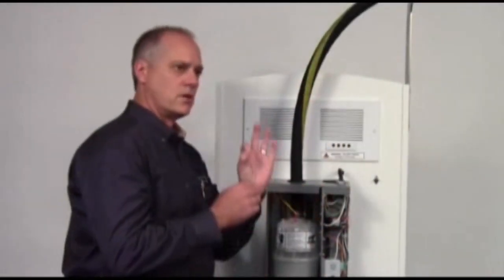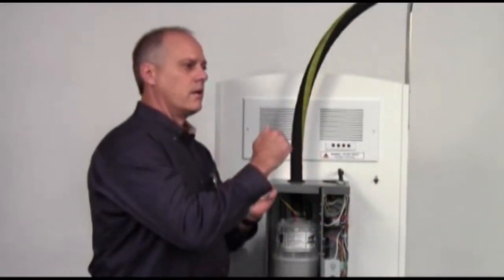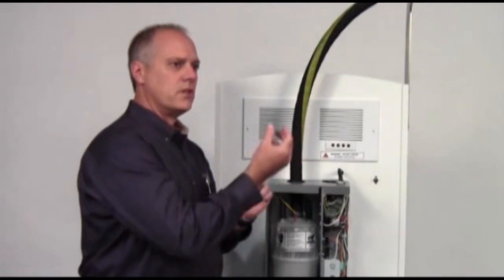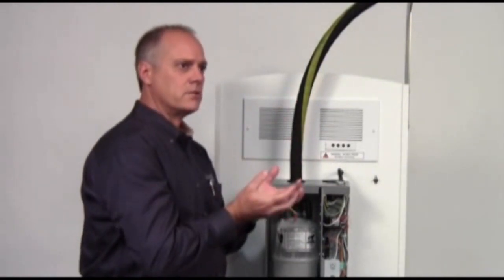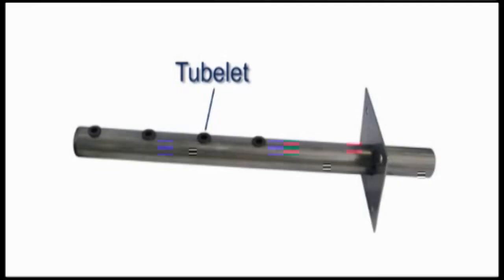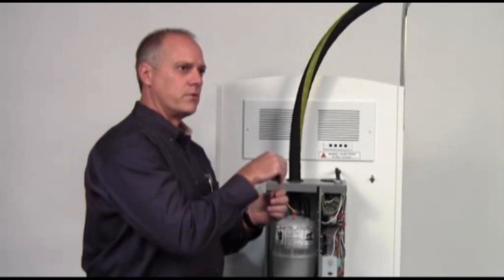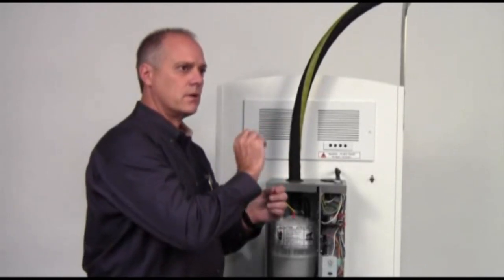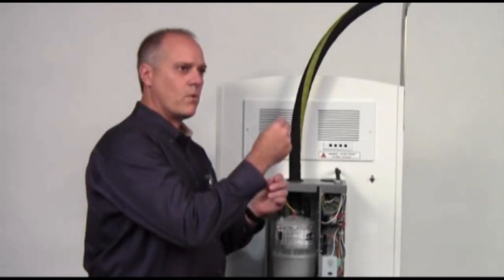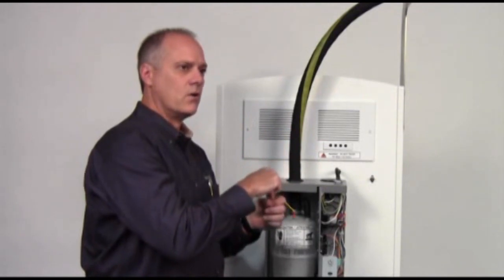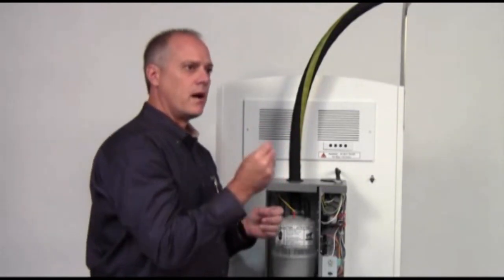Basically, how the tubelets work is you have a tube, and when you condense in there, the water can form anywhere on the inside of that tube. What the tubelets do is they extend down into the middle of that tube so that we're bringing steam out of the air, versus if the tubelet was on the edge of the steam dispersion unit, you could bring water out of there. So we're constantly bringing only steam vapor out of the holes.